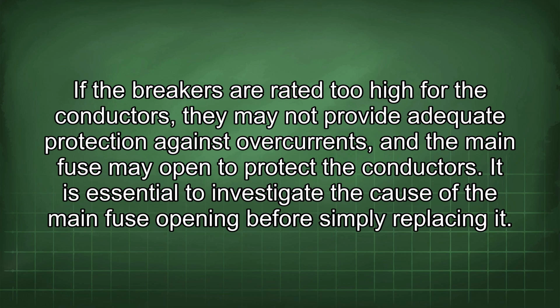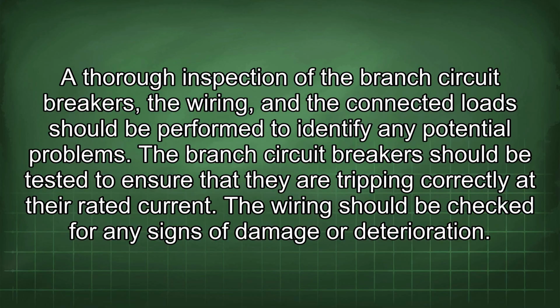It is essential to investigate the cause of the main fuse opening before simply replacing it. A thorough inspection of the branch circuit breakers, the wiring, and the connected loads should be performed to identify any potential problems. The branch circuit breakers should be tested to ensure that they are tripping correctly at their rated current.